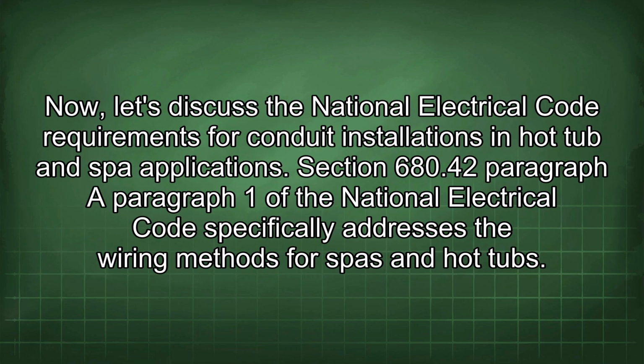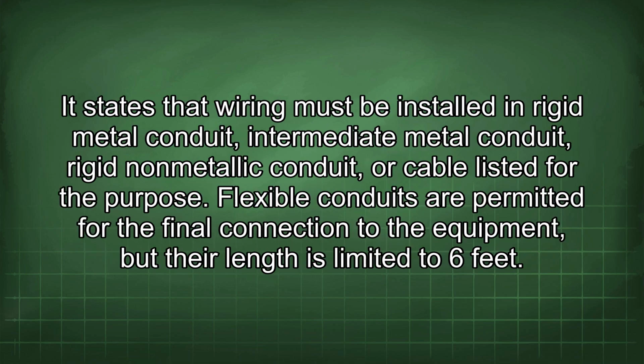Now let's discuss the National Electrical Code requirements for conduit installations in hot tub and spa applications. Section 680.42 Paragraph 1 of the National Electrical Code specifically addresses the wiring methods for spas and hot tubs. It states that wiring must be installed in rigid metal conduit, intermediate metal conduit, rigid non-metallic conduit, or cable listed for the purpose. Flexible conduits are permitted for the final connection to the equipment, but their length is limited to 6 feet.